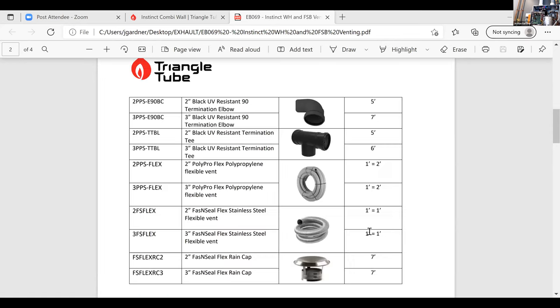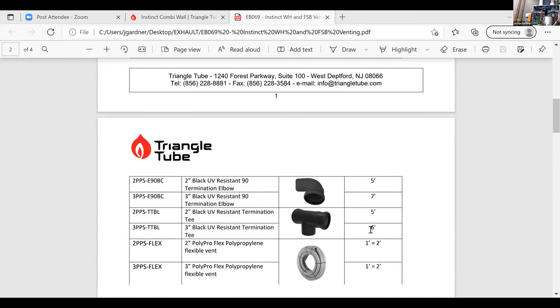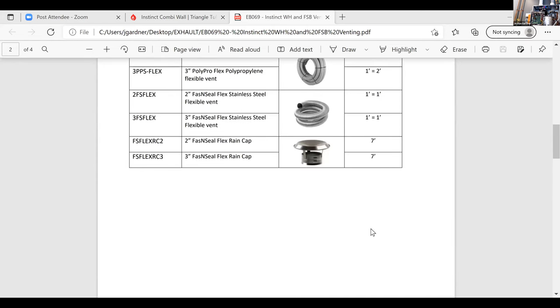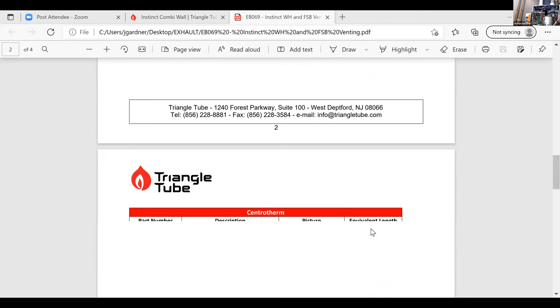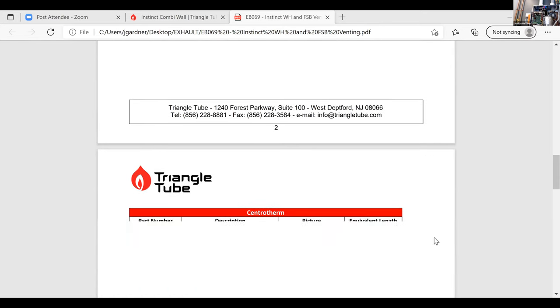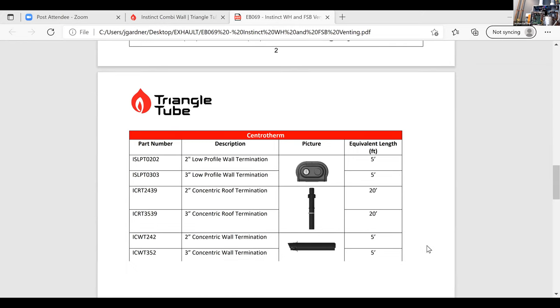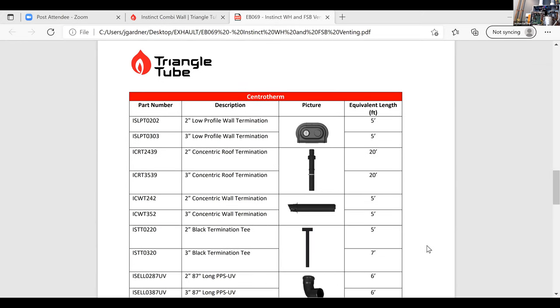We want to stay away from the bay vent ones that have the intake all the way around, or the PVC bazooka kits that exhaust 2-inch through the middle and have the intake all the way around the outside. A couple reasons. One, they don't have screens on the inlet. So we tend to find a lot of mouse nests and birds and crap in there, and that gets in through our intake system. Number two, in low fire conditions, they recirculate horribly. So we see a lot of cross-contaminations with those kits.